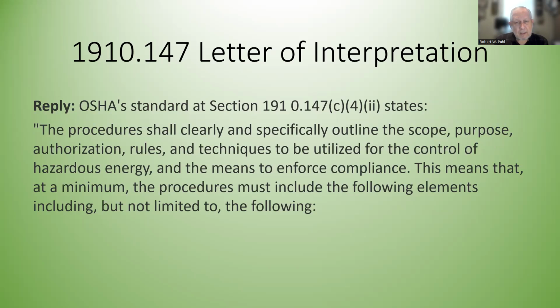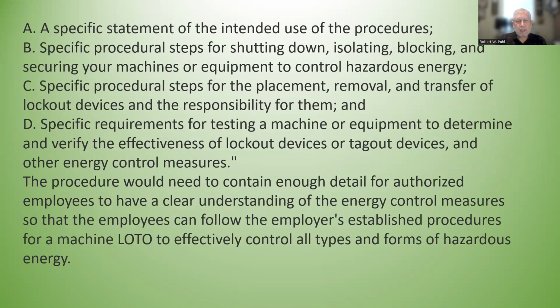The procedure shall clearly, and OSHA states, this is the reading from 1910.147(c)(4)(ii): the procedures shall clearly and specifically outline the scope, purpose, authorization, rules, and techniques to be utilized for the control of hazardous energy and the means to enforce compliance. This means that, at a minimum, the procedures must include the following elements, including but not limited to: a specific statement of the intended use of the procedures; specific procedural steps for shutting down, isolating, blocking, and securing machines and equipment to control hazardous energy; specific procedural steps for the placement, removal, and transfer of lockout devices and the responsibility for them; and specific requirements for testing a machine or equipment to determine and verify the effectiveness of lockout devices or tagout devices and other energy control procedures.